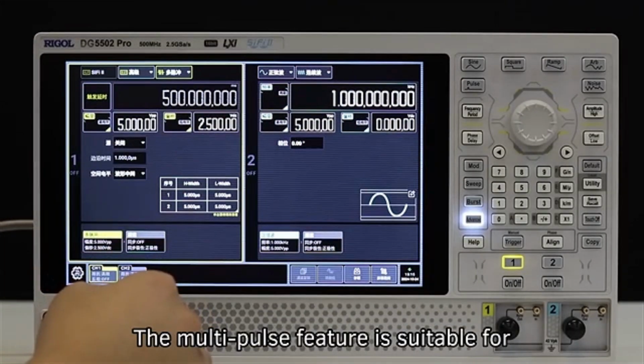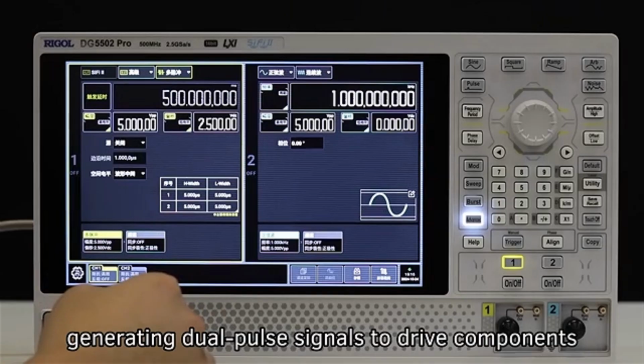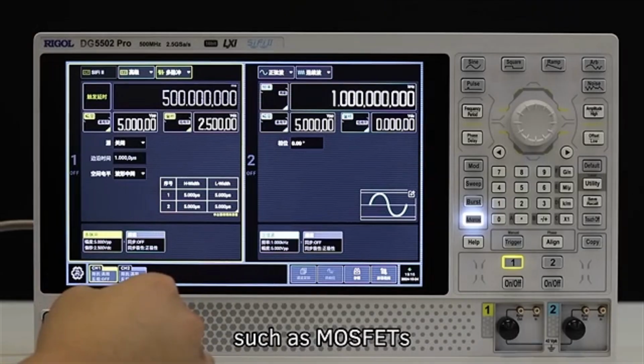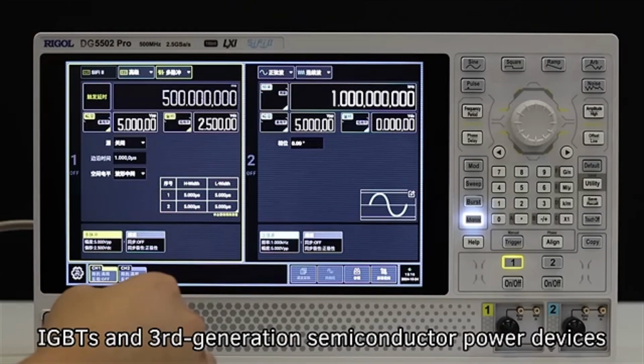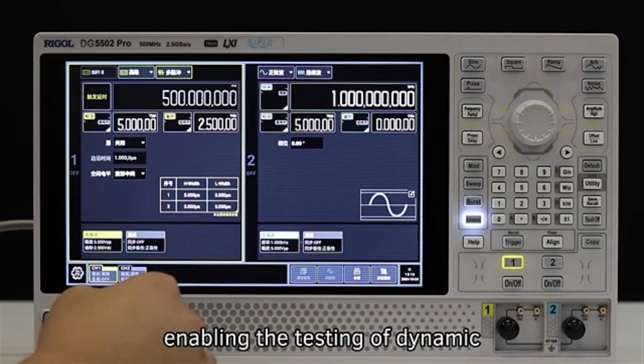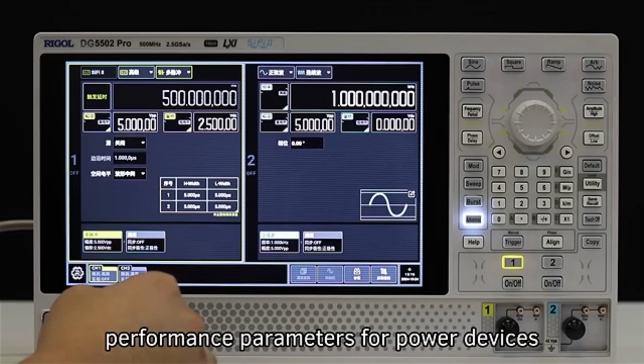The multi-pulse feature is suitable for generating dual-pulse signals to drive components such as MOSFETs, IGBTs, and third-generation semiconductor power devices, enabling the testing of dynamic performance parameters for power devices.